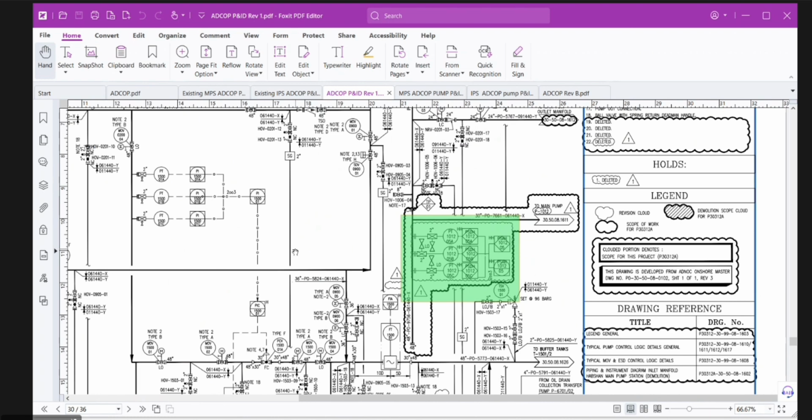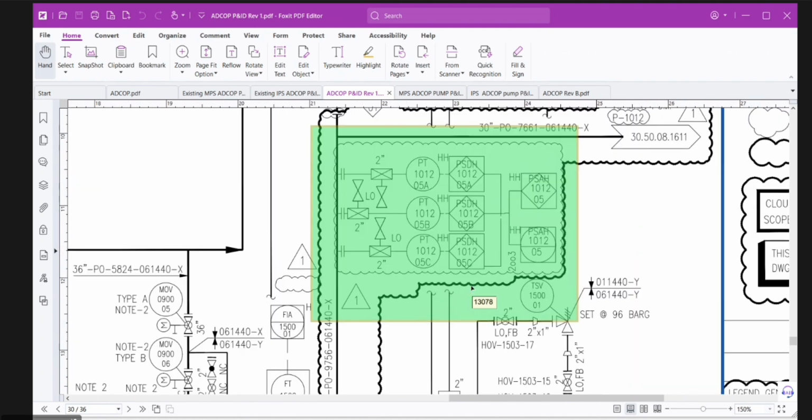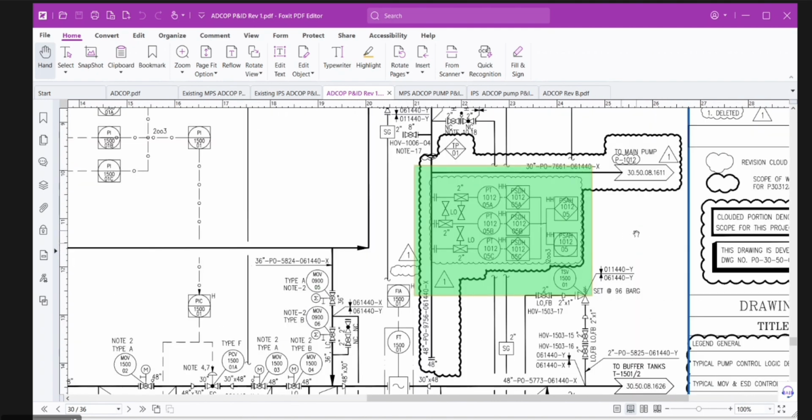Now again, this is the last opportunity for me to convince you. Do you still agree that the operator is going to be there more than 10% of the time? First look at the whole picture. On the pump section, we have added 2 out of 3 voting high pressure trip in order to avoid the scenario of shut-off pressure.